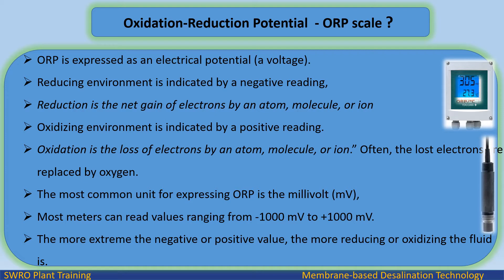Often the lost electrons are replaced by oxygen. The most common unit for expressing ORP is the millivolt, mV. Most meters can read values ranging from minus 1000 millivolt to plus 1000 millivolt. The more extreme the negative or positive value, the more reducing or oxidizing the fluid is.